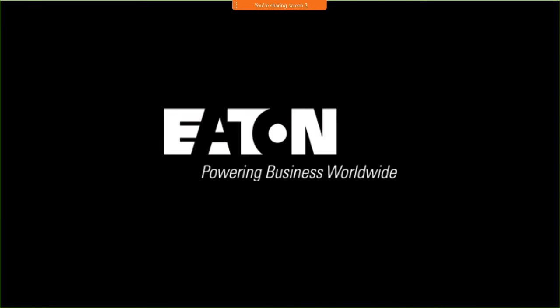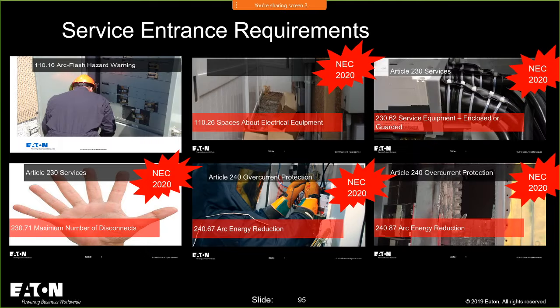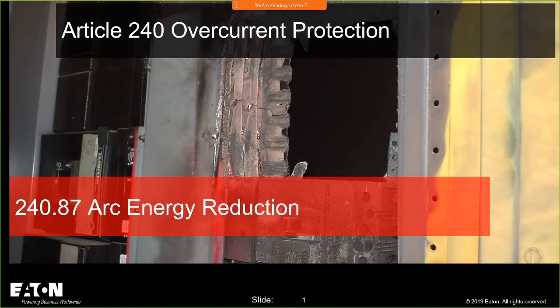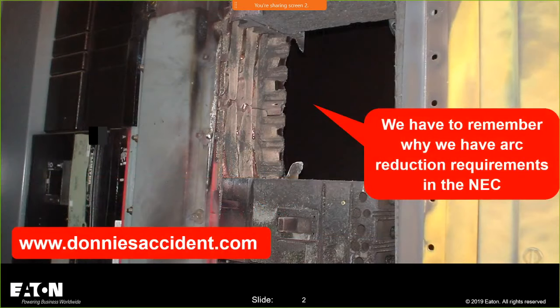240.67 and all this. Now, what I want to do is take some time and go through 240.87. Now, 240.87 saw some love. It too received attention with regard to the arcing current and making sure that the devices are set correctly and operating correctly. You have to remember why we are in this mode, because I showed you the amount of incident energy downstream in a piece of equipment can be impacted by the overcurrent device.